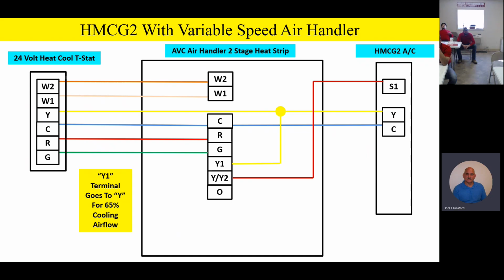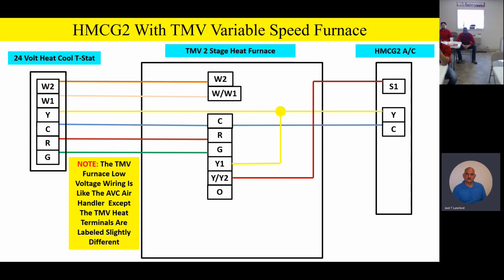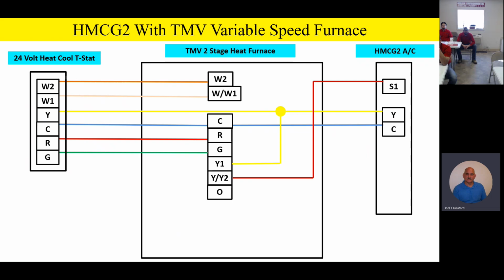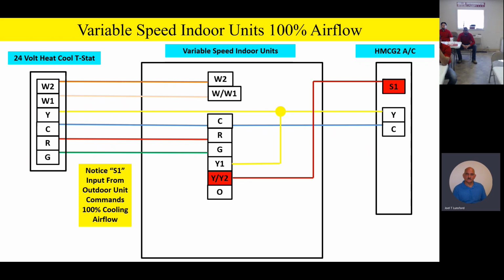And as far as the air handler is concerned, you'll see the wiring on the furnace. If you have a variable speed furnace, it wires exactly the same. The only thing you'll notice is that the terminals are slightly labeled differently. So you'll have a W/W1 for your first stage heating on your two-stage furnace. But just like we had before, guys, when you go into high airflow command, you energize that S1 signal, and it brings the indoor unit on second stage cooling airflow.